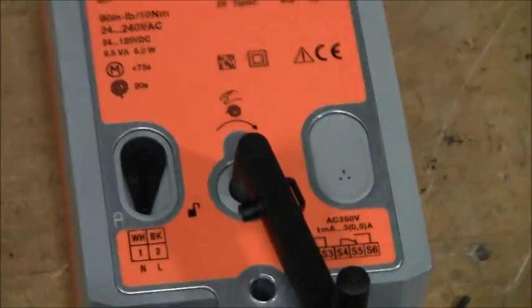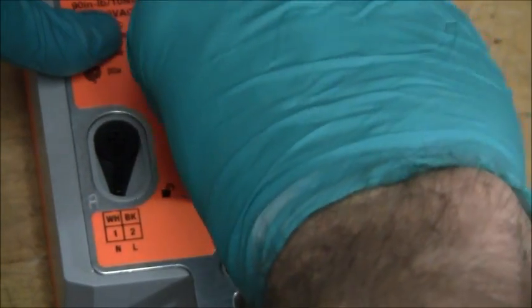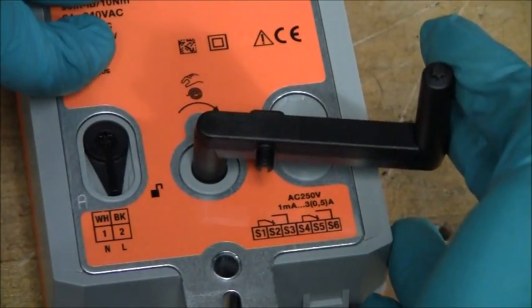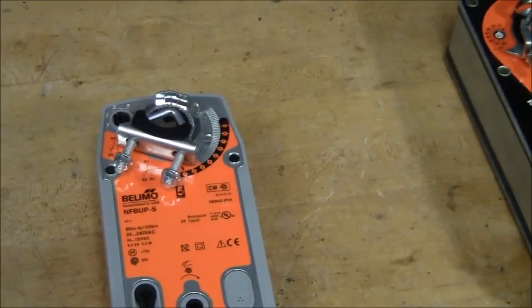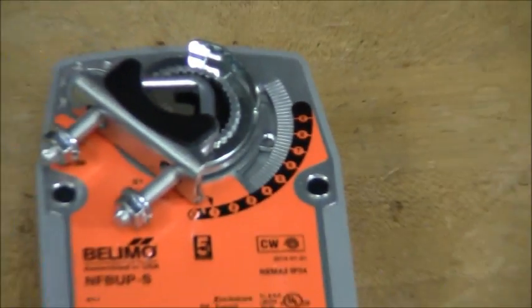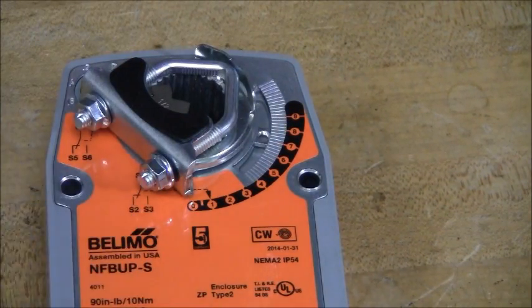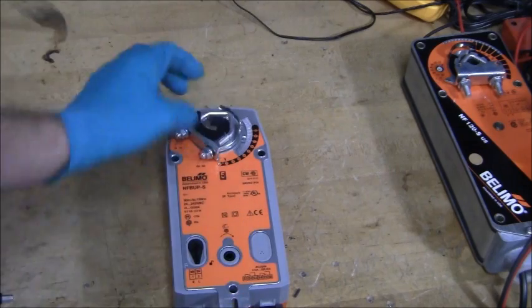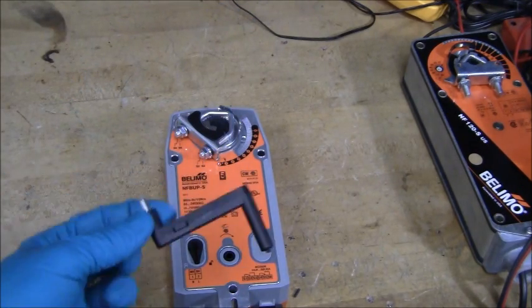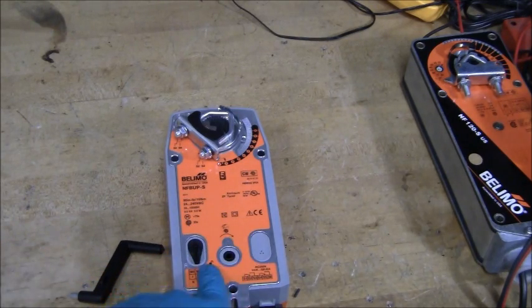I'm going to try to move the handle and you're going to see that go directly to the unlock position. You see that? Pull this out, and now the cam mechanism has been released. So now it's going back to spring tension where it's going to close. This is a normally closed situation because it's a fail safe, because it's going to a fire damper. Normally you put that when the damper is in the closed position. So the internal spring brings that to closed. But basically, that is how this override arm works and the lock and unlock feature.